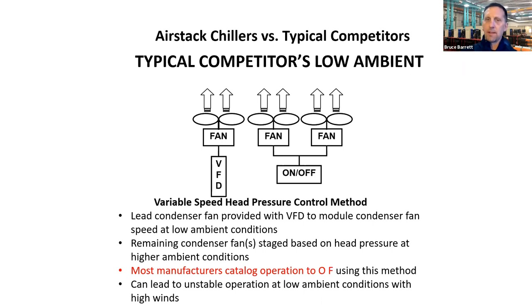The lead compressor in that array. So the best they could possibly do is typically down to 0 degrees Fahrenheit running on those low ambient conditions. Now that might be enough, but occasionally if you dip below zero, those compressors have a heck of a hard time starting. They may get liquid slugging. They may have lost all of their refrigerant in their condenser, and it's hard to get that back. Don't have enough lift from those compressors to push everything back.